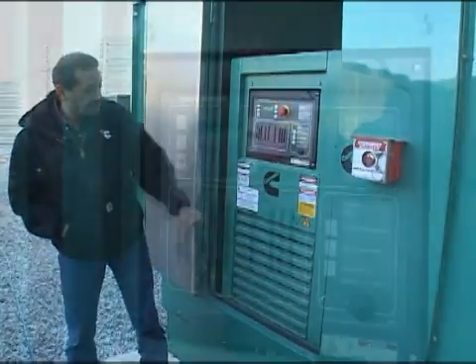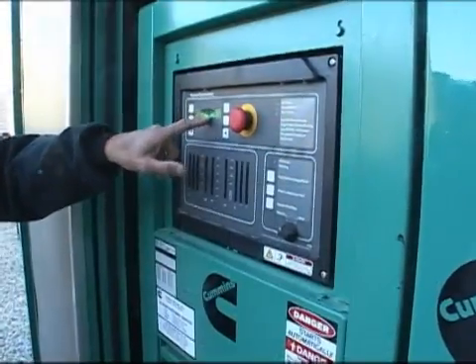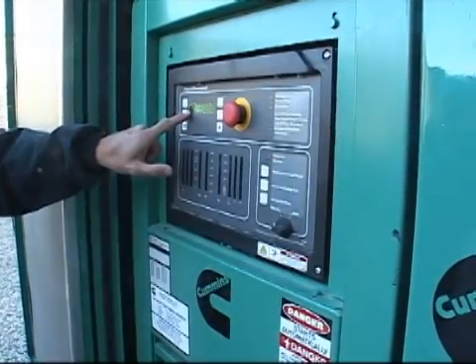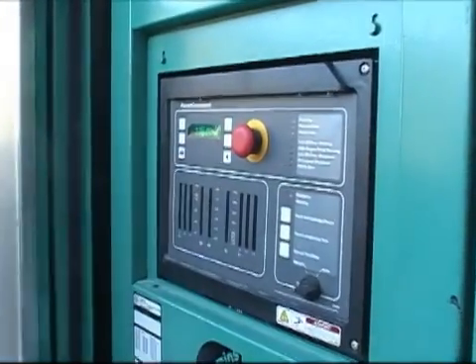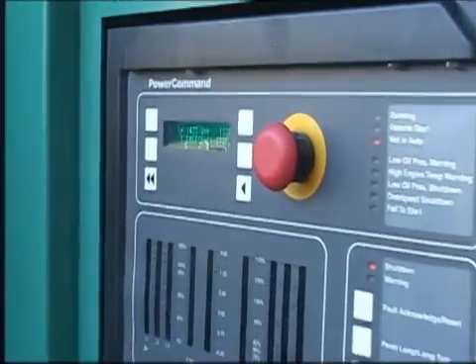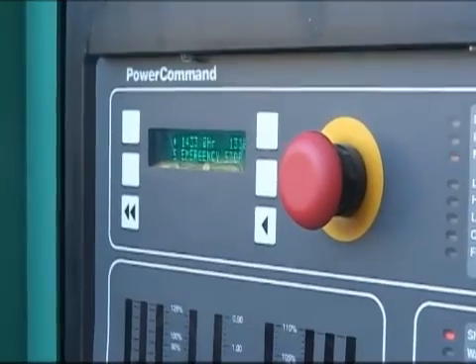What I'm going to do is create one. I just created a shutdown fault — emergency stop, basically. Tells me that in case you didn't know. So now when you go back in there, you notice 'current' has an arrow next to it. When I go into current it's telling me what the current alarm is, so if someone came in and pushed a button you could get back in there and find out what it was.